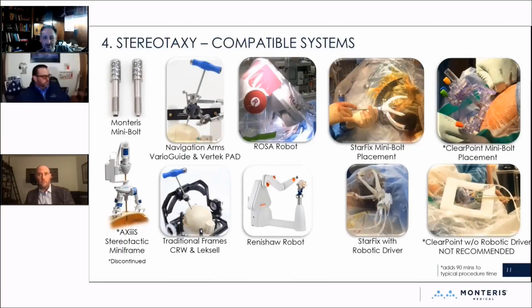When you compare those systems, and we see a bunch of them here, they're pretty much all the same. They are, on the order on a phantom of, a half millimeter accurate, whether it's a Leksell frame or a Starfix or a Renishaw, Rosa robot, etc. A little bit less than that is something that is not rigidly affixed, like the navigation arms that you see. But for most things, if you're not going for a very long pass or a very small lesion, the accuracy of those is more than adequate.